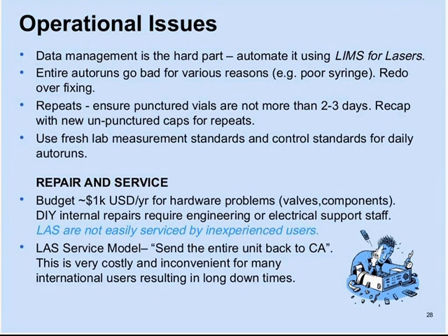Often it's valves internal in the instrument, or electrical components, hard drive failures, these sorts of things. I've seen pretty much all of those. The other thing is that DIY, do-it-yourself internal repairs really require some sound engineering and electrical support staff. They are kind of black boxes for a reason. If you open it up, you may be baffled by what you see. I would suggest that they're not easily serviced by inexperienced users.